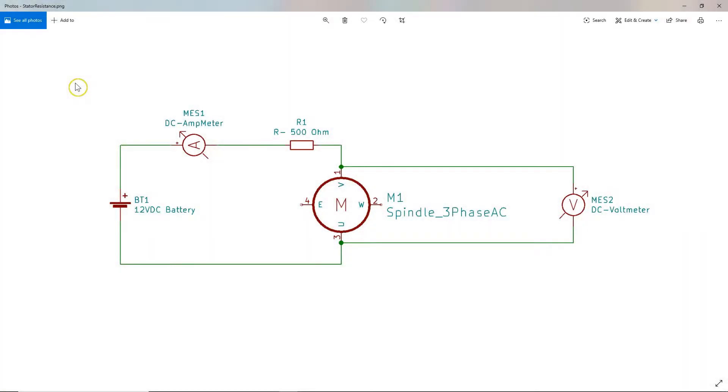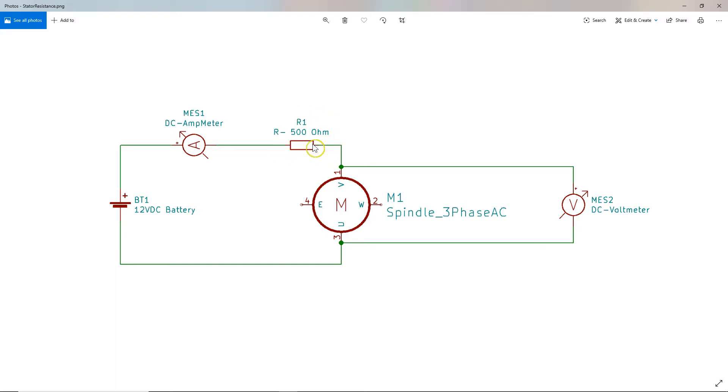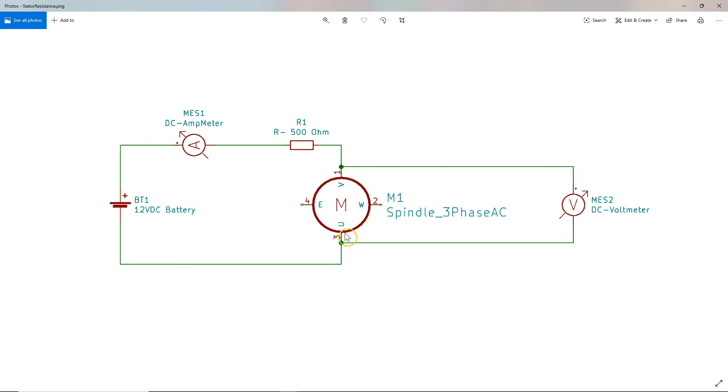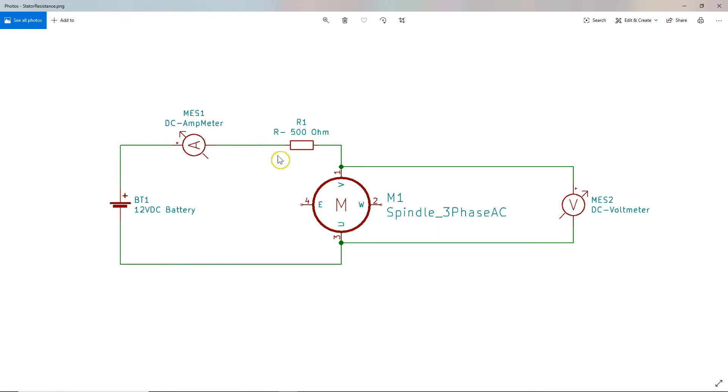Here's a schematic of the setup that we have. This is the 12-volt battery wired directly into this amp meter which is in line with the circuit measuring the current. Then we head over to this 500-ohm resistor. The only reason this resistor is here is to limit the amount of current flowing through this circuit so that we don't short out the battery. Then we come directly into the windings of the motor. In this case we're doing the winding between V and U. This second voltmeter is just here to measure the voltage drop across the winding. You want these probes to be just across the winding that you're trying to measure the resistance of. You're trying to isolate it. Once we have that, we know the current that's running through here and we know the voltage drop across the winding, so using Ohm's law we should be able to calculate the resistance.